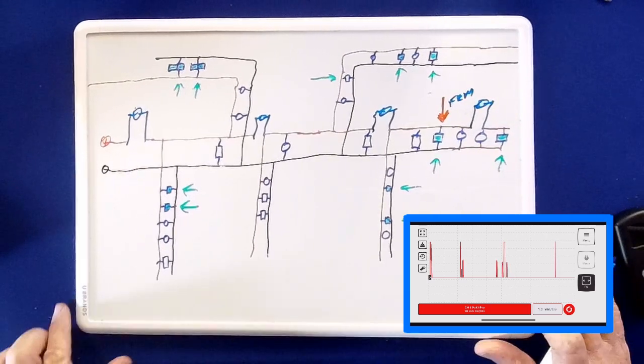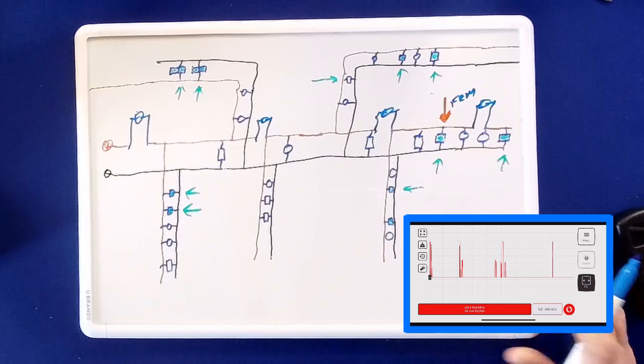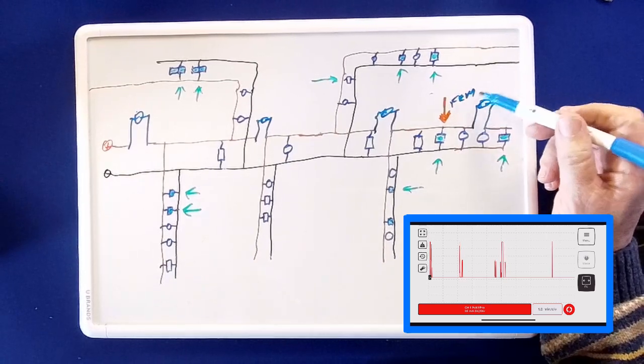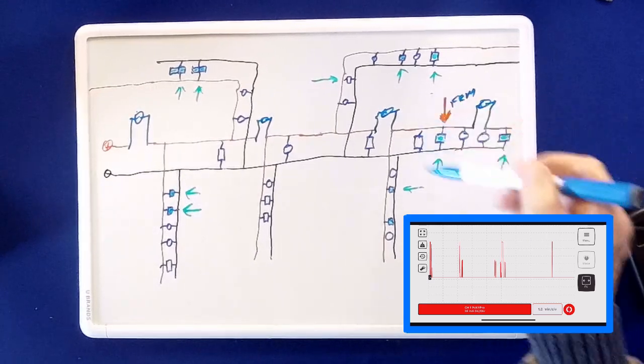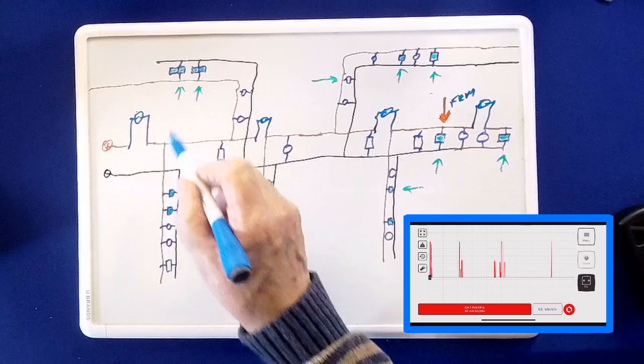I'm not saying that the mini modules or the single or dual modules don't do it. It's very rare for a mini module to do it. It's more common for an FDM or a dual module than it is for a single module. But by far, it's been the FRM. So we don't know what's there, but now I'm going to tell you how you find out.